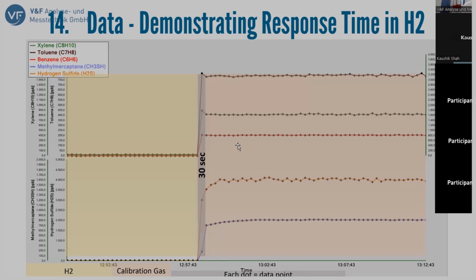This is a demonstration of how fast the system will respond to a change of signal. Here we have applied a calibration gas containing BTX, methyl mercaptan, and hydrogen sulfide. Before, we were applying pure hydrogen, then switching to the calibration gas. You see that within one cycle of all the compounds, depending on the stickiness of the compound, we are immediately at the expected level which comes from this cylinder. There are some compounds which take a little more flush time, like this one here, hydrogen sulfide. But we will go into flush times in more detail when we do the live demonstration.